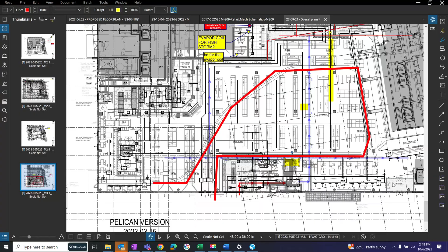So when you don't have the makeup air units dedicated like you've shown us, a lot of times they might want us to interlock with the exhaust fans, so that when your exhaust fans are off, we can adjust our outside air. But if that's not needed, you can just say no. You can still do it for the seafood department, though, Barb. Oh yeah, 1500, I forgot about that. Thank you. So if you want it, we can. That's right.